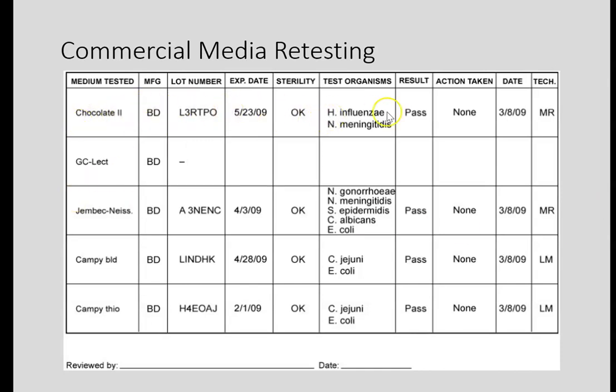For chocolate agar, you have to put Haemophilus influenzae and Neisseria meningitidis on there and make sure they both grow. GC media, which is gonococcus media, and Jembec, which is also a Neisseria gonococcus medium — you need to check all these things because yeast will sometimes grow on it. Other Neisseria species will also grow on it, but we're specifically looking for Neisseria gonorrhoeae when we're trying to recover.